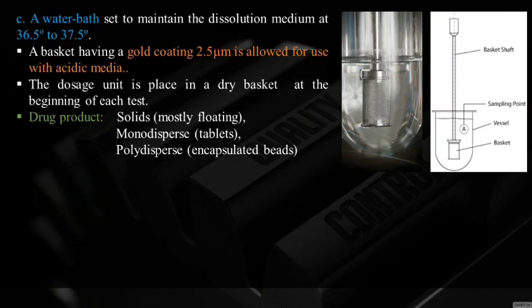Agitation speed is 50 to 100 rpm. The water bath maintains the dissolution medium at 36.5 to 37.5°C. A basket with a gold coating of 2.5 micrometers is allowed for use in acidic medium, since acidic medium may corrode the basket. The dosage unit is placed in the dry basket at the beginning of each test.